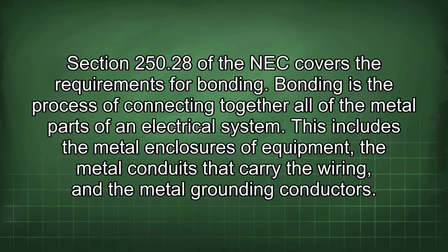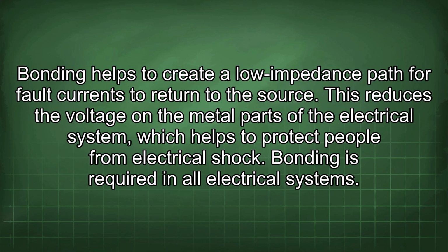Bonding is the process of connecting together all of the metal parts of an electrical system. This includes the metal enclosures of equipment, the metal conduits that carried the wiring, and the metal grounding conductors. Bonding helps to create a low impedance path for fault currents to return to the source. This reduces the voltage in the metal parts of the electrical system, which helps to protect people from electrical shock. Bonding is required in all electrical systems.